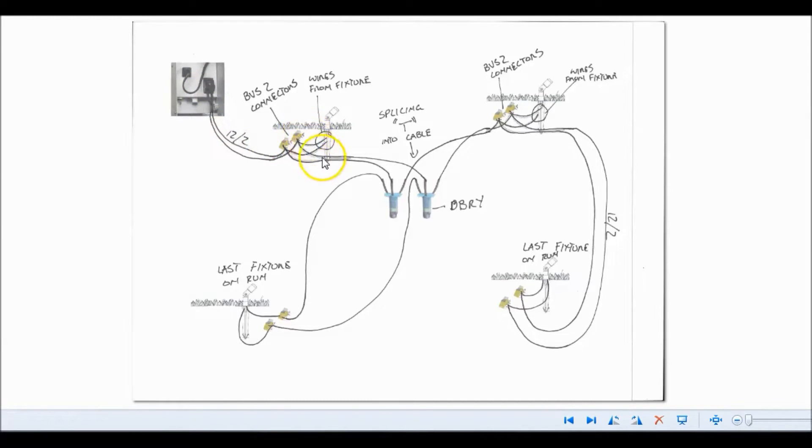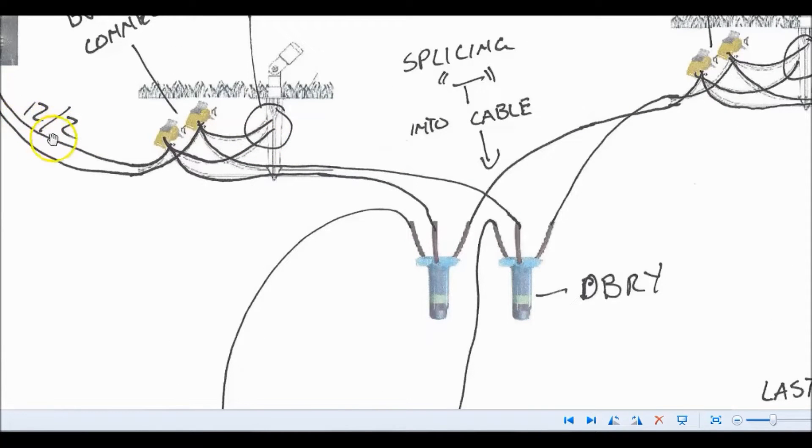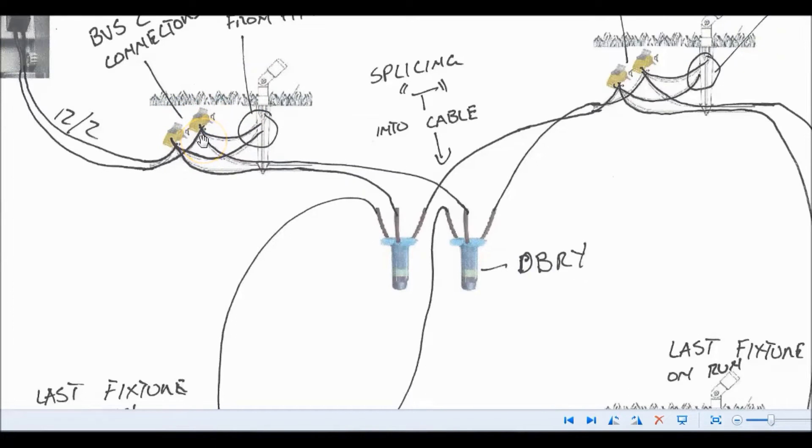Then you run it out to your existing fixture. One of those wires from the 12-2 is going to go into your Bus 2 snap lock connectors, and then there's another port where another one is going to come out and connect to the next fixture. Then you have a smaller port that will have your wire from your fixture going into it. So in essence, you're going to have three wires going into each one of these. At each light, you've got one wire going in, one wire going out, and then your fixture wire coming in — you have two of those connectors at every light.